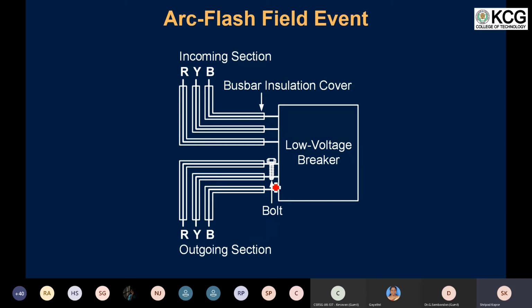Because of the fault that occurred due to this particular bolt, it initially started as a phase-to-phase fault, but gradually the phase-to-phase fault on the outgoing leg converted into a three-phase fault, because the arc spread to the third conductor as well. And since in LT switchgear you do not have a compartment between the outgoing leg and the incoming leg, the arc further spread to the incoming side of the breaker. So now the phase-to-phase fault converted into a three-phase fault on the outgoing leg as well as a three-phase fault on the incoming leg.